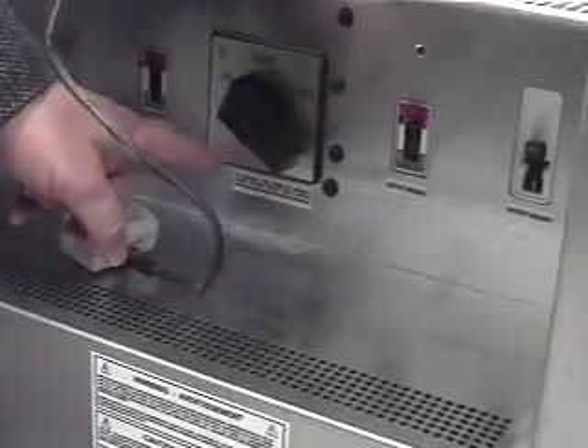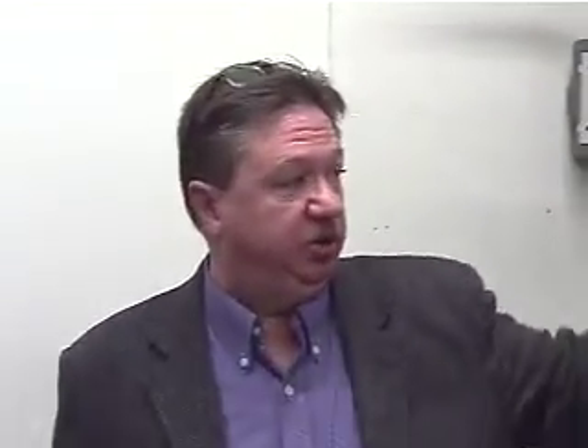Two things to note and always remember: when you shut the UPS down completely, you can put it over to bypass mode to wrap around the unit, because it's a hard path around it. Then the rest of it can be completely shut down and taken control of.